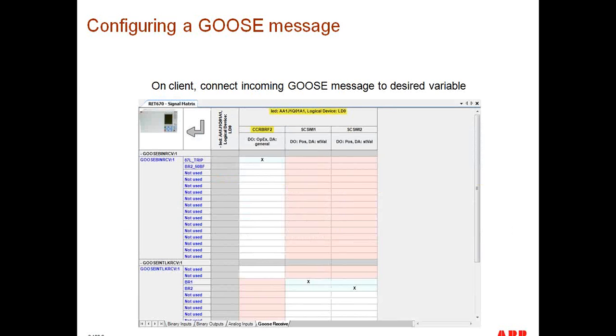When we do a Goose message, it's essentially the same thing as wiring an output contact and then wiring it to the physical input of a relay. What that particular device receiving that information does is not within the scope of what a Goose message is. A Goose message is just a mechanism to share that bit of information. How that information is tied, whether to a breaker fail function or to the trip function, is up to the software of each individual relay.